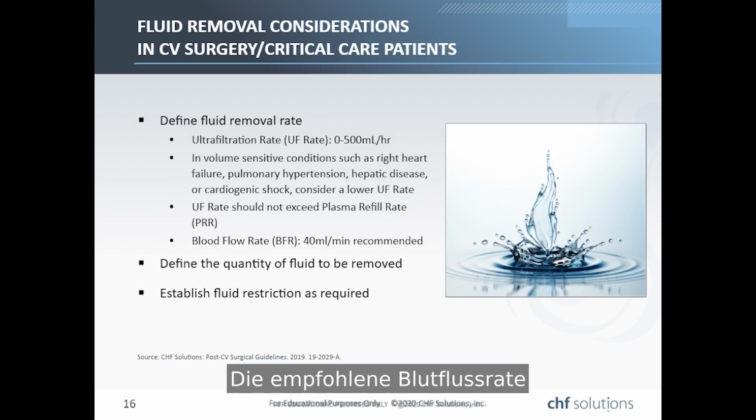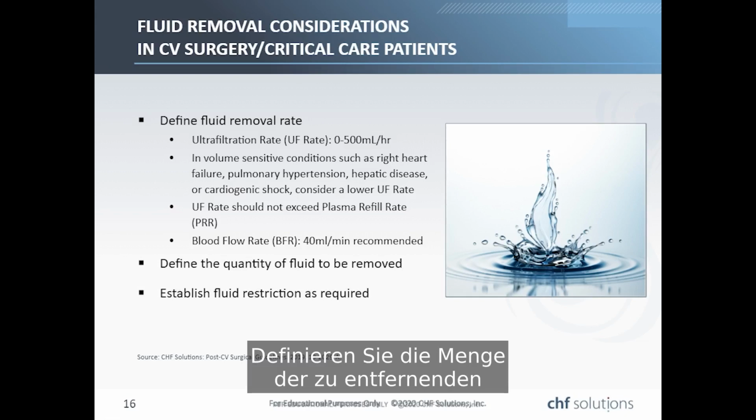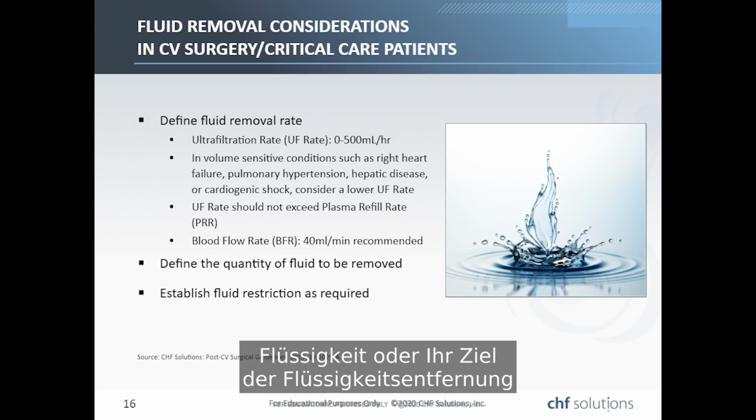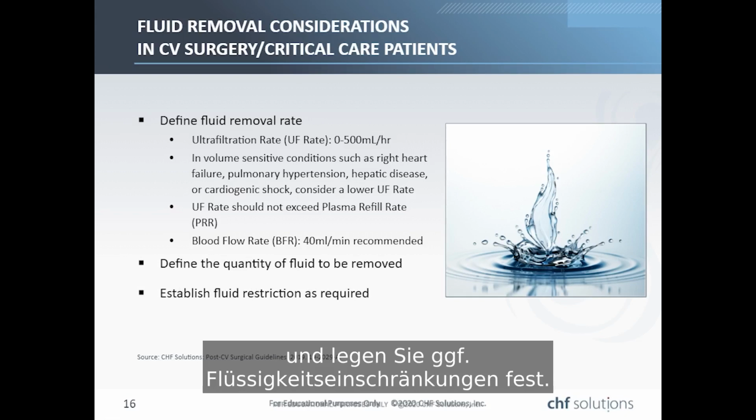The recommended blood flow rate is 40 milliliters per minute. Define the quantity of fluid to be removed, or your fluid removal goal, and establish fluid restrictions as required.